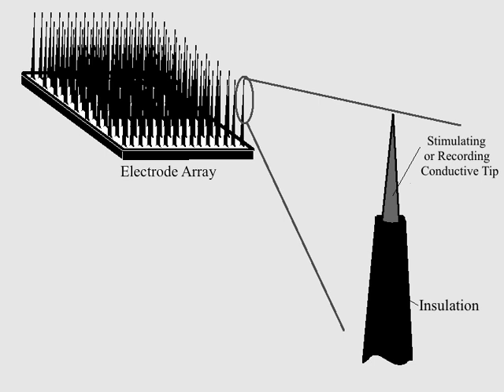Knowing the impedance of an electrode is important whether the electrode is used for stimulation or recording. When degradation of the electrode surface occurs because of corrosion, the surface area increases with its roughness. Calculating a new electrode impedance to compensate for the change in surface area once implanted is not easy. This computational flaw can skew data from recording or pose a dangerous obstacle limiting safe stimulation.